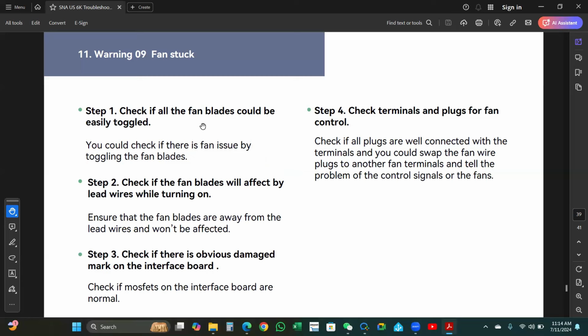Warning 09, fan stuck. Step 1. Check if any of the fan blades could be easily toggled. You could check if there is a fan issue by toggling the fan blades. Step 2. Check if the fan blades are affected by lead wires when turning. Ensure that the fan blades are away from the lead wires and won't be affected.